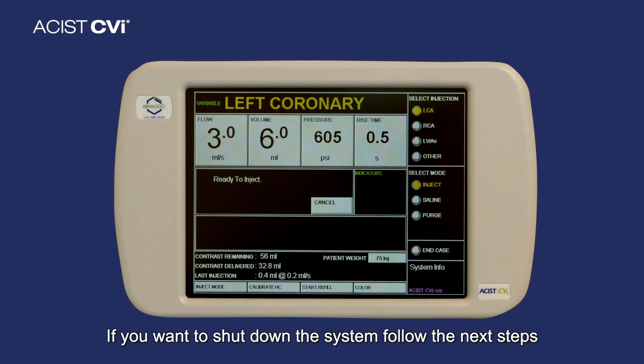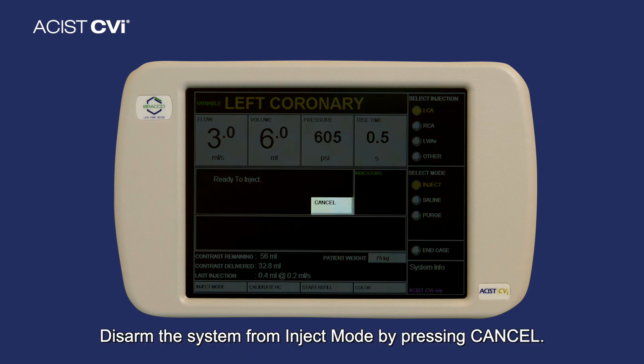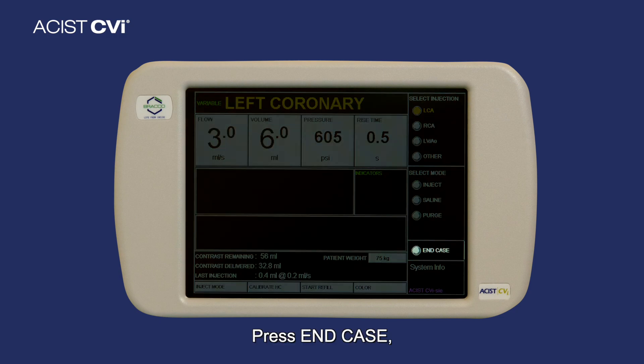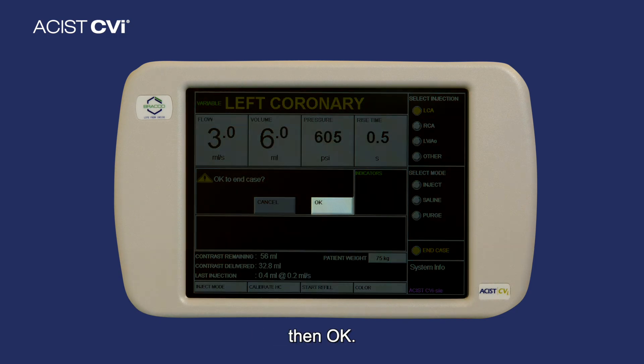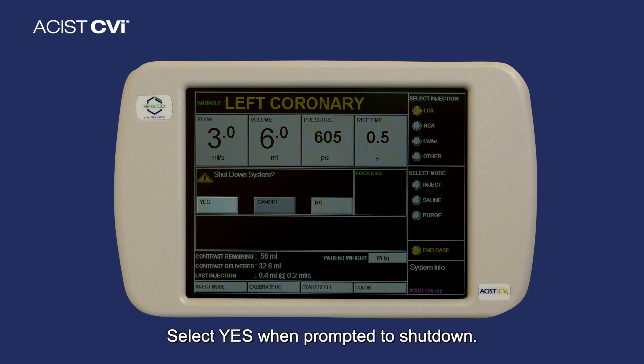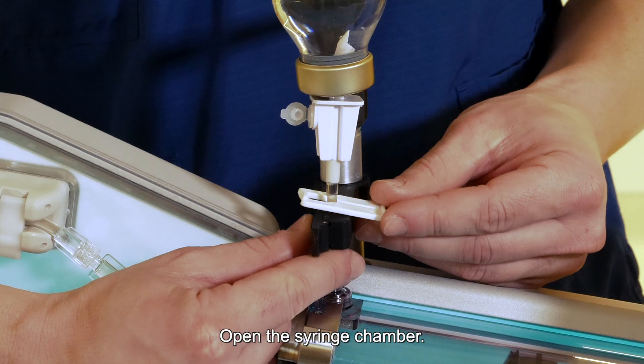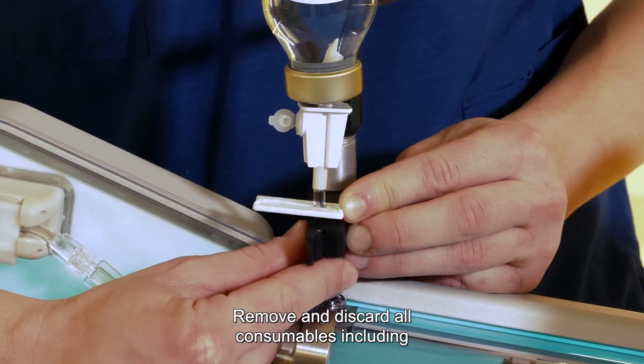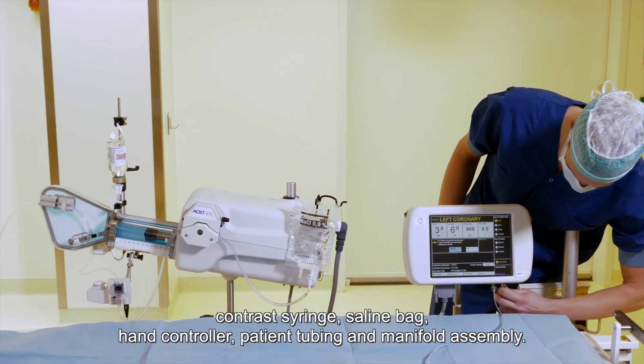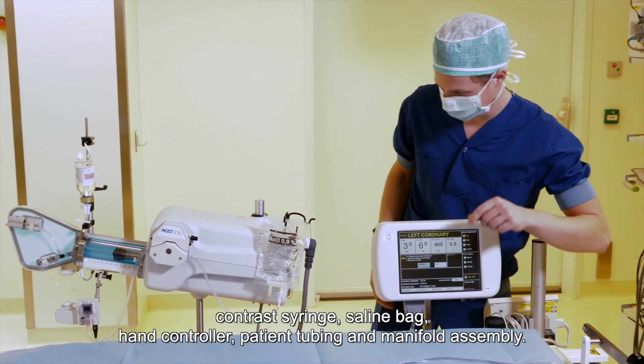To shut down the system, follow the next steps. Step 1: disarm the system from inject mode by pressing cancel. Step 2: press End Case, then OK. Step 3: select Yes when prompted to shut down. Open the syringe chamber, remove and discard all consumables including the contrast syringe, saline bag, hand controller, patient tubing, and manifold assembly.